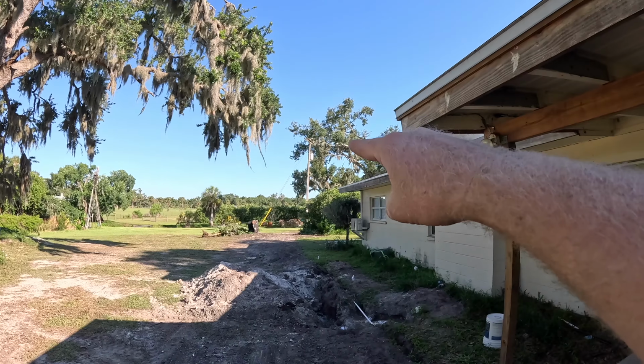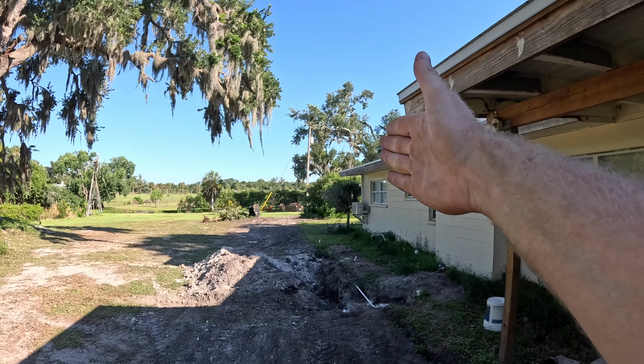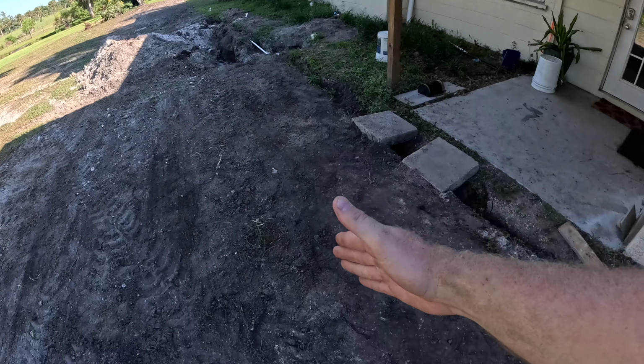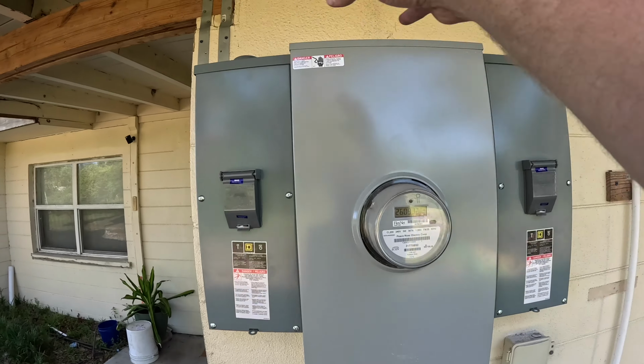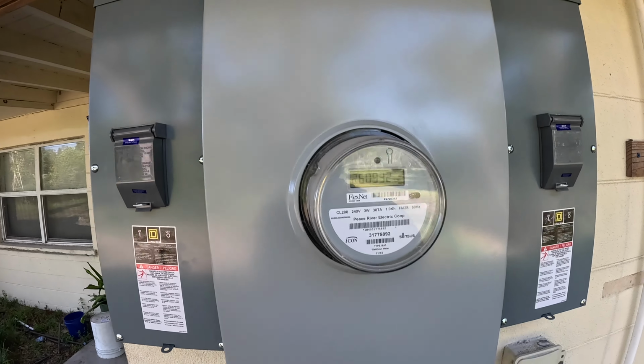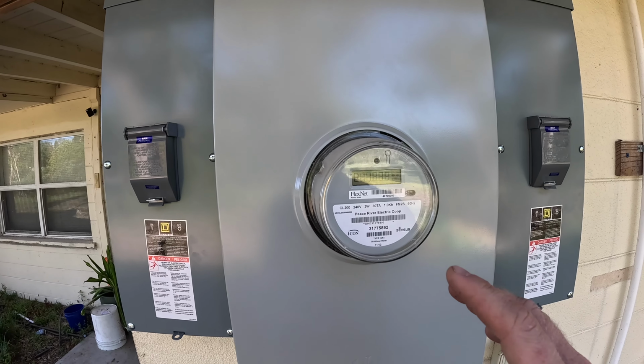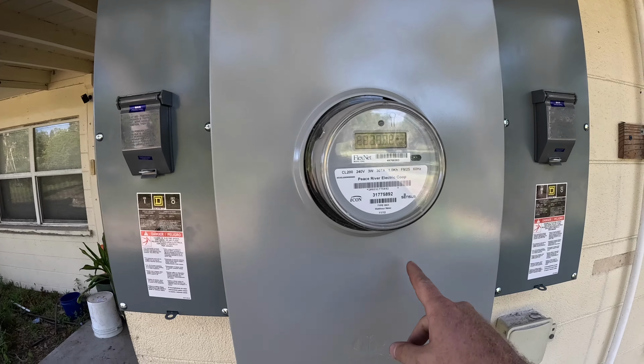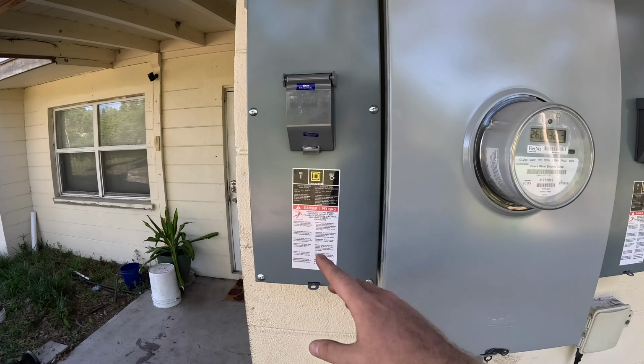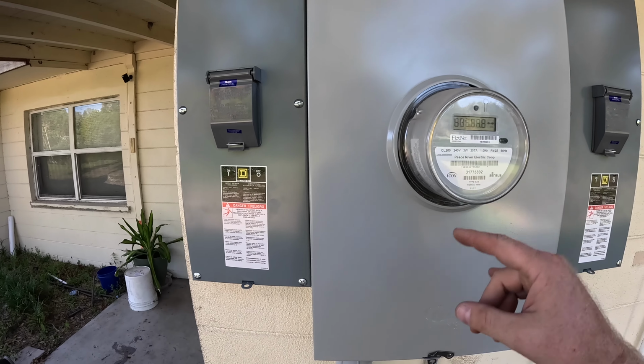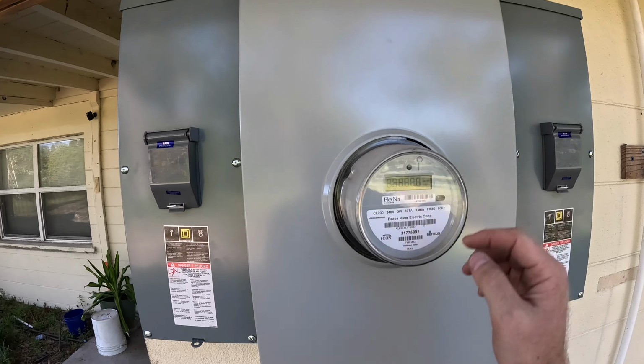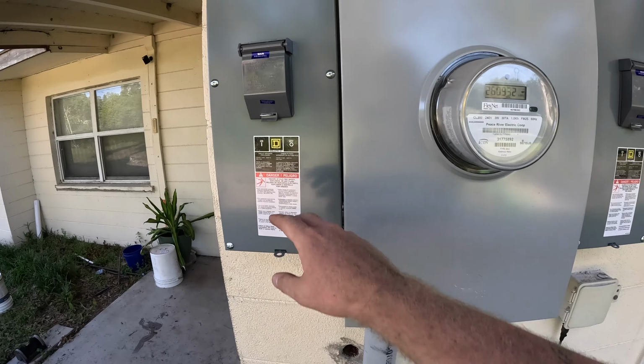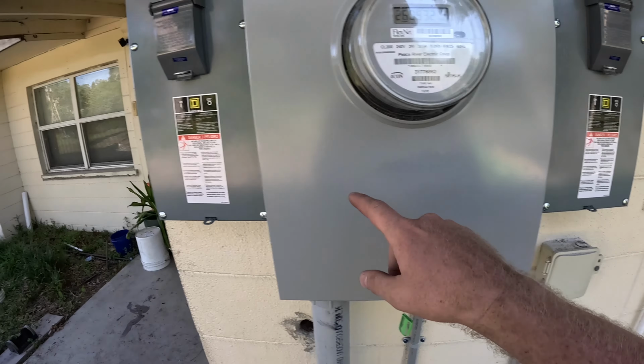New 25 kVA transformer, 350 kcmil wire, trenched all the way to right here into the top of the new meter base. Meter remained the same. Then we have, I believe, 3/0 copper to each disconnect, and that's 3 separate 3/0 copper because you have 2 hots and a neutral coming in the top, 2 hots and a neutral coming out the bottom. You also have your ground wire connected between the two.